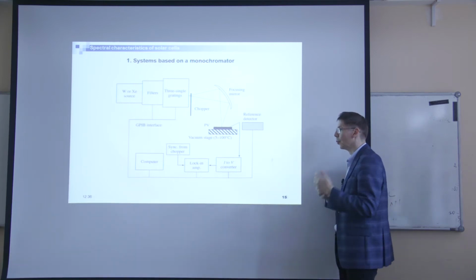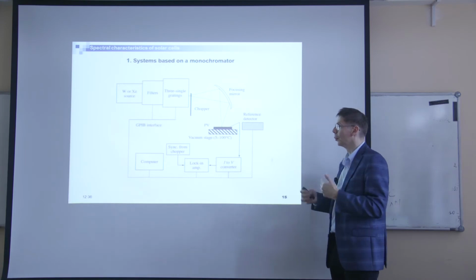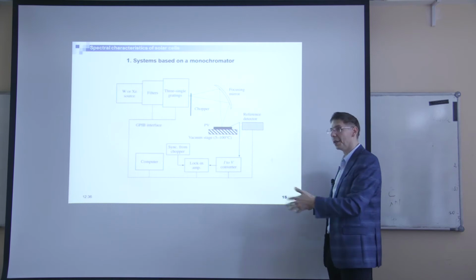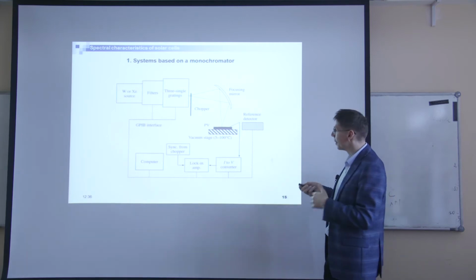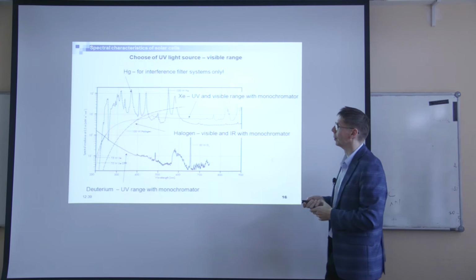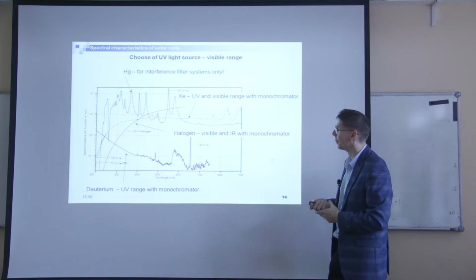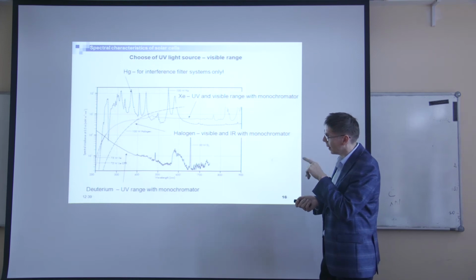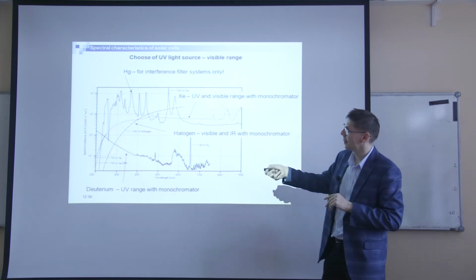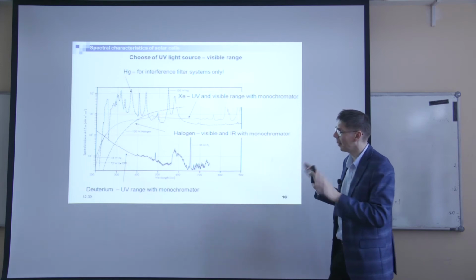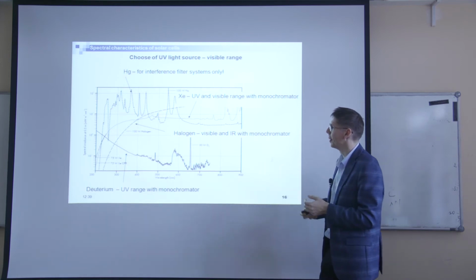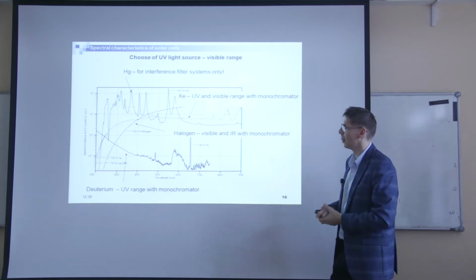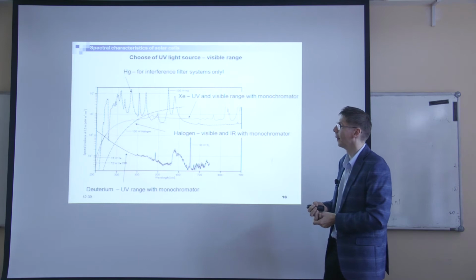If you start to measure with some system, first of all you have to get some idea about whether it is stable in time, etc. But in any case, it's better to check its intensity. Actually, it's always so for any type of lamp, whether it is a halogen or xenon lamp, it has temperature dependence. It's a very important thing.